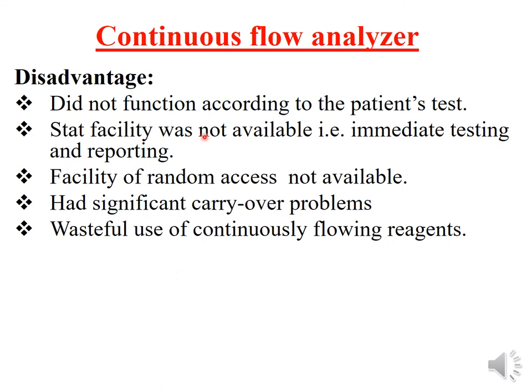The disadvantages of continuous flow analyzers are that they do not function according to the patient's test — you cannot complete all tests of one patient at a time. There is no STAT facility, meaning if any sample needs to be done on an emergency, you cannot change your preference.